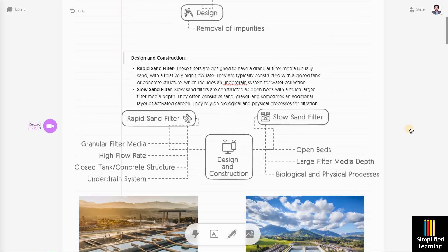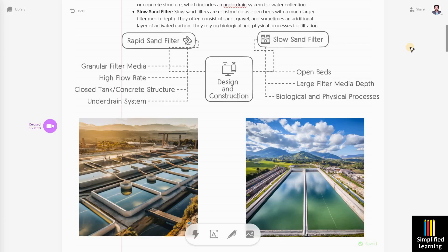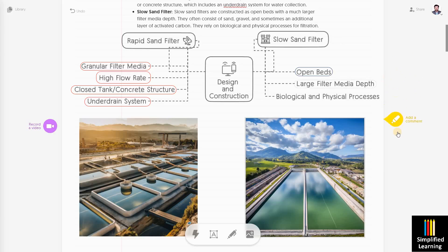The first criteria is design and construction. In rapid sand filter, the design consists of granular filter media, and the flow rate is very high. It may use a closed tank or concrete structure, and the water passes out via an underdrain system. Whereas slow sand filter has a very high surface area requirement, large filter media depth, and the operation is both a biological and physical process.